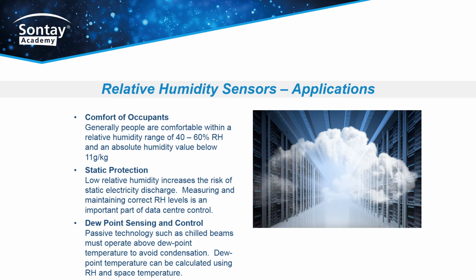Dew point sensing and control. Passive technologies such as chilled beams must operate above dew point temperature to avoid condensation. Dew point temperature can be calculated using RH and space temperature.